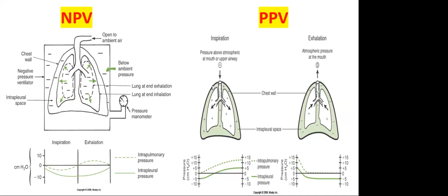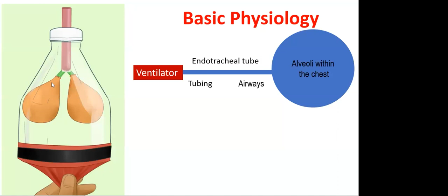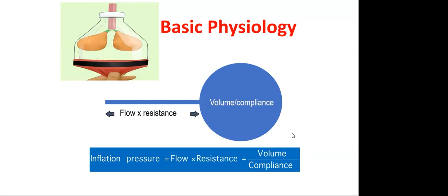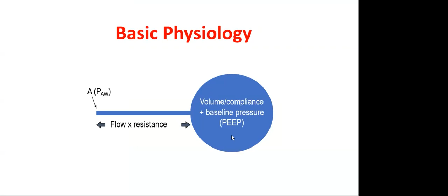So the lung-ventilator unit can be thought of like a tube. You can see here a tube inside a bottle with two balloons. If you want to blow air inside it, you have to overcome the tube resistance, and also whatever minimal pressure is already there in the balloons. In medical terms, that is the flow and resistance of the ET tube and the airways you have to overcome. And the alveoli are like a balloon, which has some compliance. So you have to overcome the volume and compliance, plus the baseline pressure in that balloon itself. All these things together are called the inflation pressure. So flow times resistance, that is the tube, plus volume divided by compliance, plus baseline pressure.